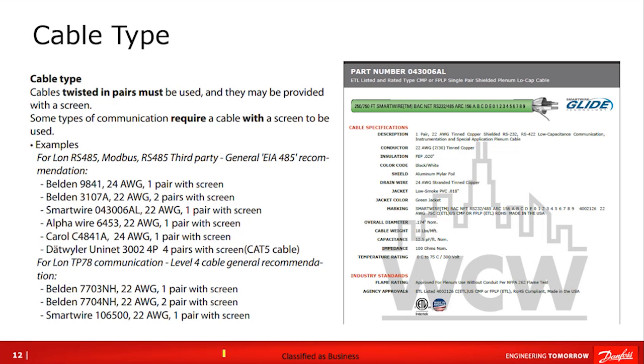Cable types are very important. For Echelon 485 and Modbus, the general requirement is an EIA 485 rated cable. Some examples are listed here — most commonly used on the market today is Windy City Wire, labeled as smart wire. Ultimately it needs to be EIA 485 rated to match all the specifications the controllers expect. If we don't use a cable that matches the spec, we have a higher risk of data loss and nuisance communication alarms.